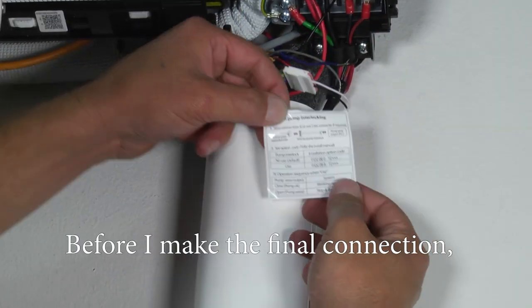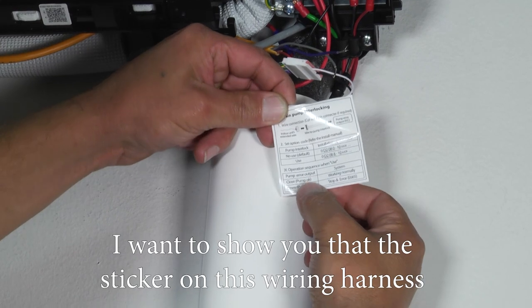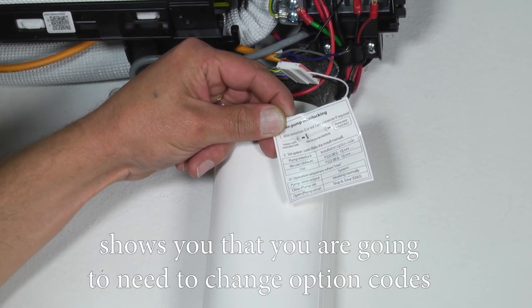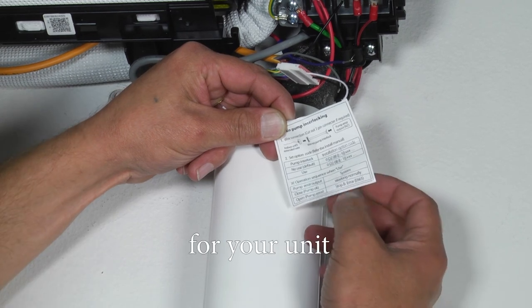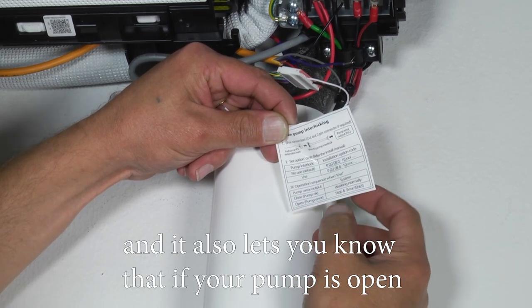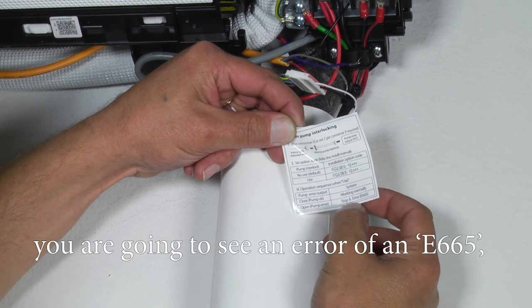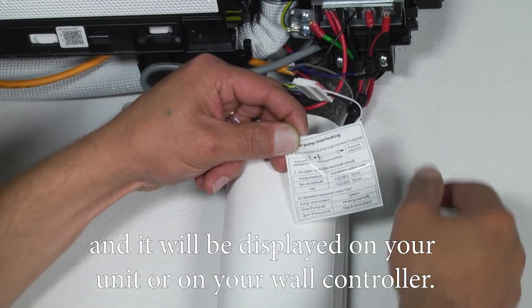Before I make the final connection, I want to show you that the sticker on this wiring harness shows you that you're going to need to change option codes for your unit. And it also lets you know that if your pump is open, you're going to see an error of an E665 and it'll be displayed on your unit or on your wall controller.